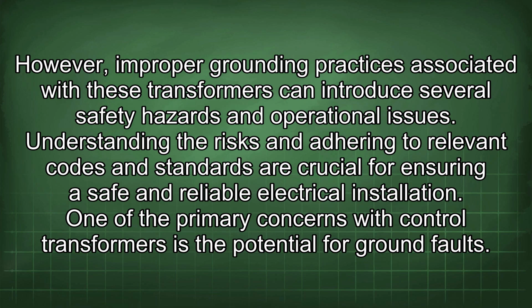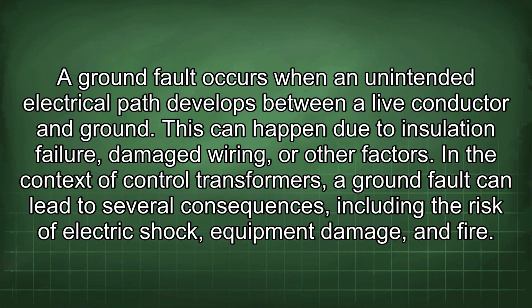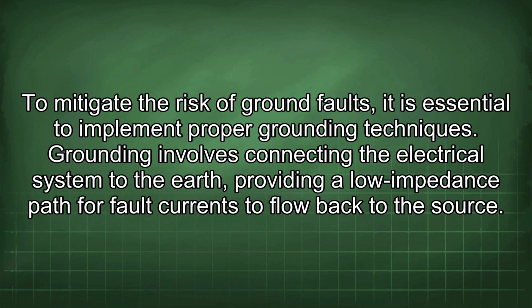One of the primary concerns with control transformers is the potential for ground faults. A ground fault occurs when an unintended electrical path develops between a live conductor and ground. This can happen due to insulation failure, damaged wiring, or other factors. In the context of control transformers, a ground fault can lead to several consequences, including the risk of electric shock, equipment damage, and fire. To mitigate the risk of ground faults, it is essential to implement proper grounding techniques.